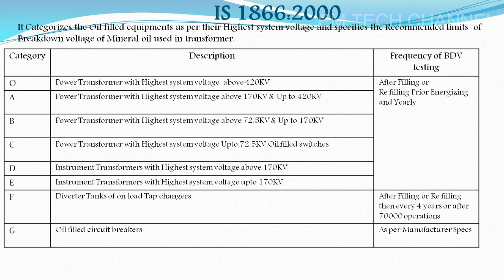And as I said before, current transformers and potential transformers, called instrument transformers, with highest system voltage above 170 kV fall in the D category, and instrument transformers with the highest system voltage up to 170 kV fall in the E category, provided these instrument transformers are of oil filled type. Diverter tanks on on-load tap changers come under the F category, and oil filled circuit breakers fall in the G category.